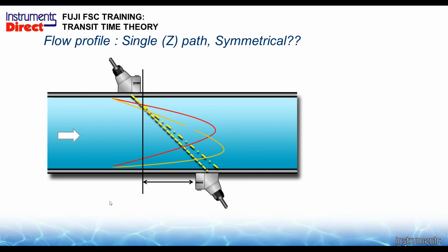Should I not have my proper straight run of pipe, then the flow profile is distorted and may actually kick my signal downstream. Now, depending on how far it gets kicked downstream, I may or may not pick up the signal. So if I do my calculation like I'm supposed to, and I don't have enough straight run of pipe, and I put my two sensors on, and I get no reading, I will have to move my sensor, or prospect my sensor, say in quarter-inch increments, to find that sweet spot. Now, once I begin to prospect for a signal, that means a couple of things. One, I don't have enough straight run of pipe. Two, there's an anomaly inside the pipe, a chunk of something, or the pipe's not round, so the math is off. Now, once I move off this button, the calculated space there, I may be able to get a reading, but it's not at the optimum accuracy that was quoted for this device.